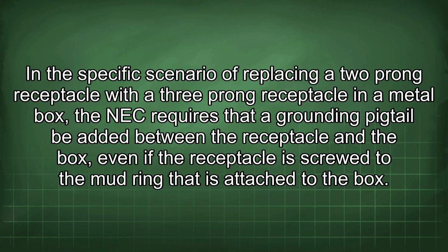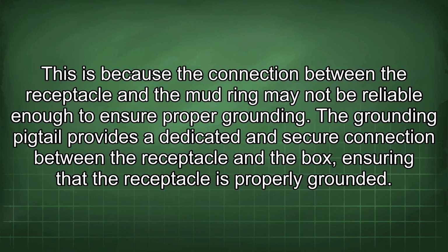In the specific scenario of replacing a 2-prong receptacle with a 3-prong receptacle in a metal box, the NEC requires that a grounding pigtail be added between the receptacle and the box, even if the receptacle is screwed to the mud ring that is attached to the box. This is because the connection between the receptacle and the mud ring may not be reliable enough to ensure proper grounding. The grounding pigtail provides a dedicated and secure connection between the receptacle and the box, ensuring that the receptacle is properly grounded.